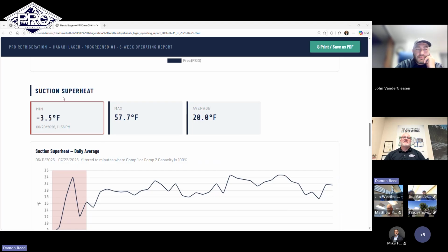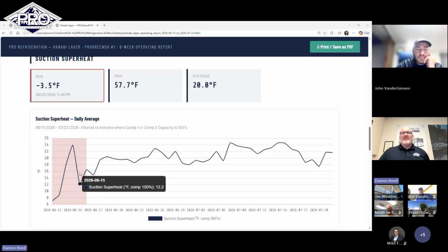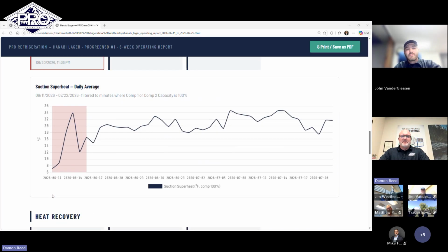We had our suction superheat that we're looking at. That tied right in as well with the service event. So suction superheat dropped way off. That would happen because your suction pressure drops way off. So everything starts to get unhappy. It tells you.